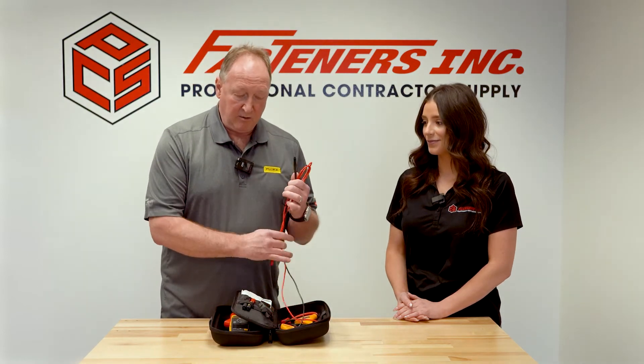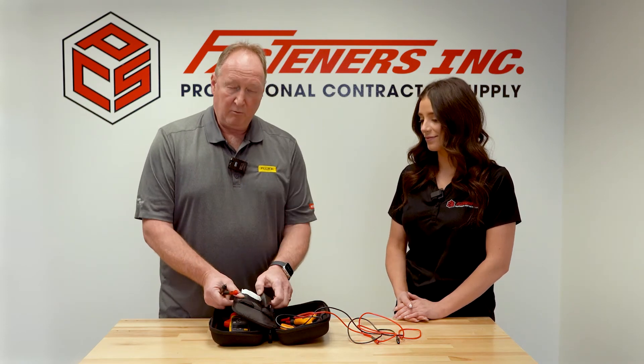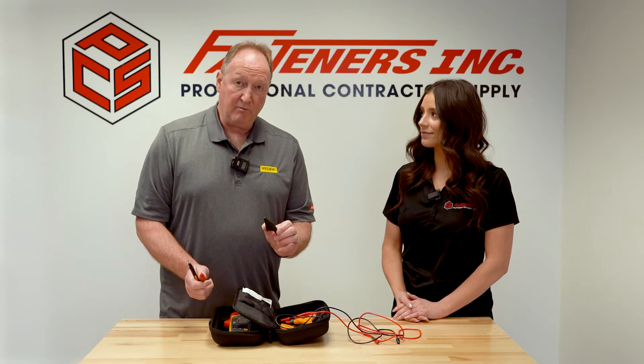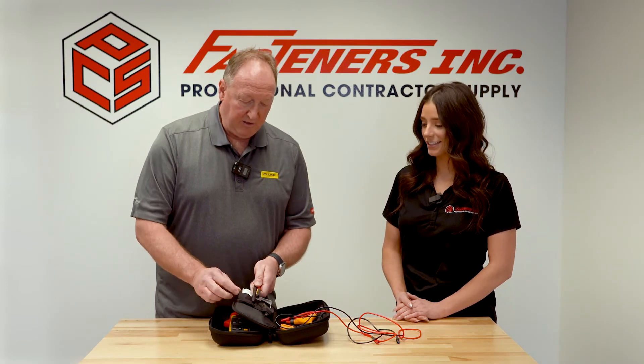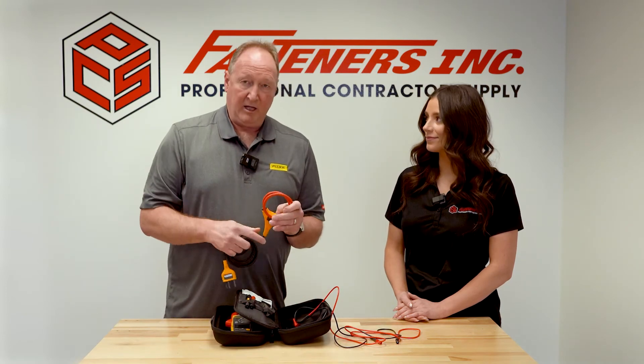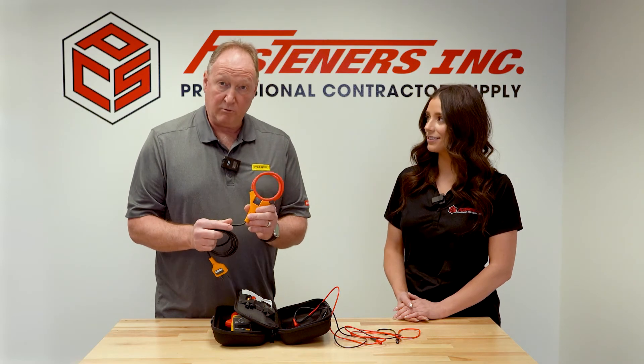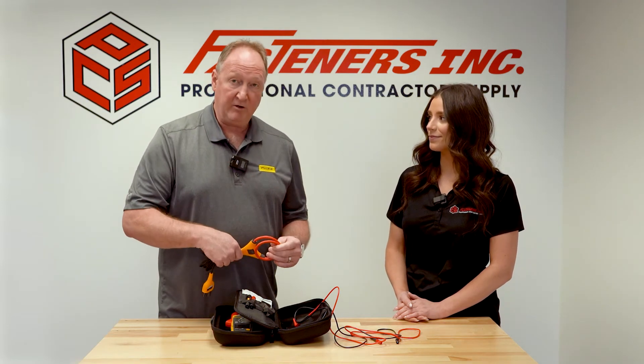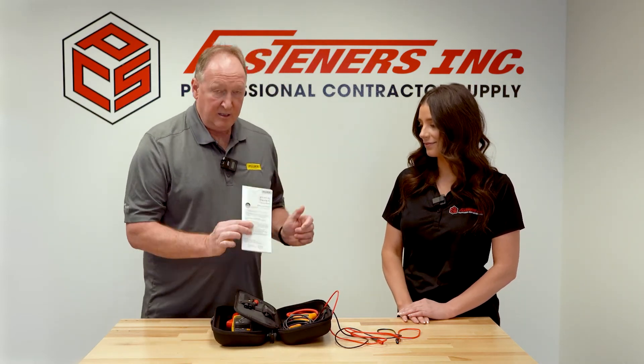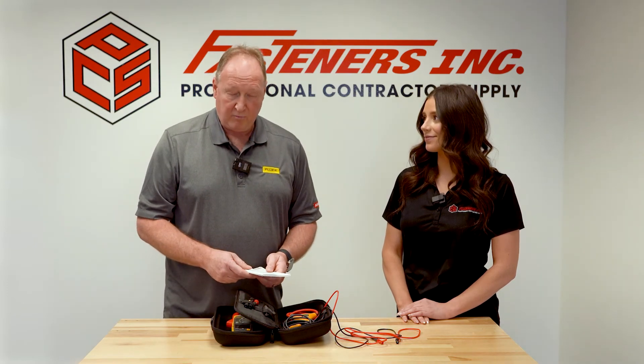You're going to have your test leads and your new test probes. With this meter, you're going to need an alligator clip when you make your voltage and current measurements — you get that ground reference. And then finally, it comes with a flexible current clamp. It's a 2500-amp current clamp that comes standard with the unit — you can measure up to 2500 amps AC. And with all of our products, safety first, so we're going to give you our safety literature to make sure you know how to use the product correctly.